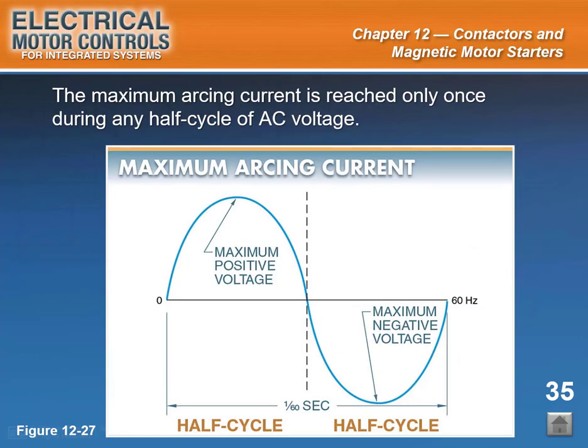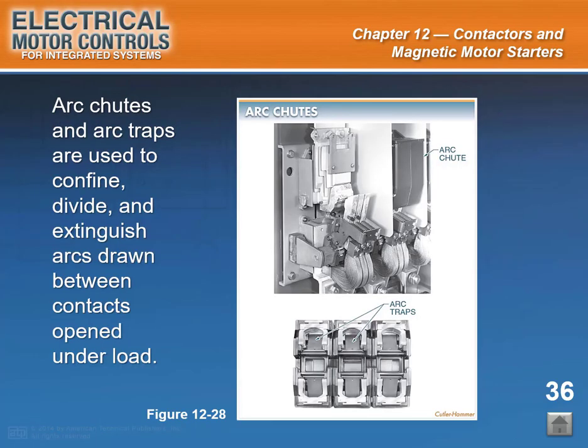Slide caption: the maximum arcing current is reached only once during any half cycle of AC voltage. See Figure 12-27. An AC arc is self-extinguishing when a set of contacts is opened. In contrast to a DC supply of constant voltage, an AC supply has a voltage that reverses its polarity 120 times a second when operated at a line frequency of 60 Hz. The alternation allows the arc to have a maximum duration of no more than a half cycle. During any half cycle, the maximum arcing current is reached only once. End of slide 35. Start of slide 36.